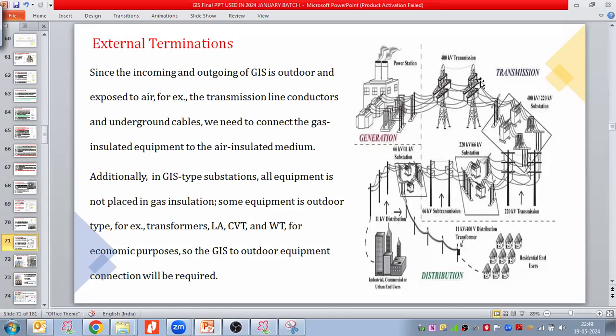Now if you see here, we are taking an example of the grid. Here we have generation, then the transmission line, and then it enters the substation. When this line connects to the GIS, there is a requirement for terminations. The incoming and outgoing of the GIS is outdoor type, exposed to air. For example, the overhead transmission conductors, underground cables and transformers are all outdoor. So we need to connect gas insulated equipment to air insulated equipment. For that purpose, we require external termination equipment in GIS substations.